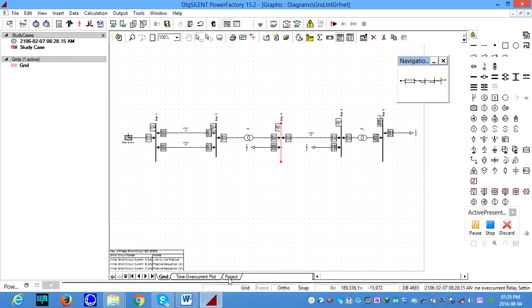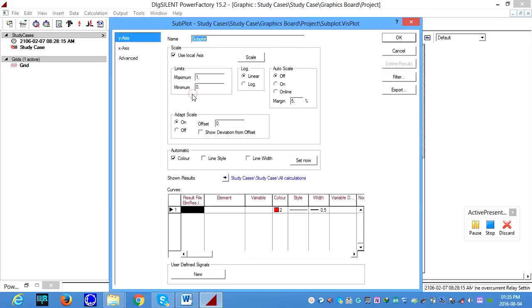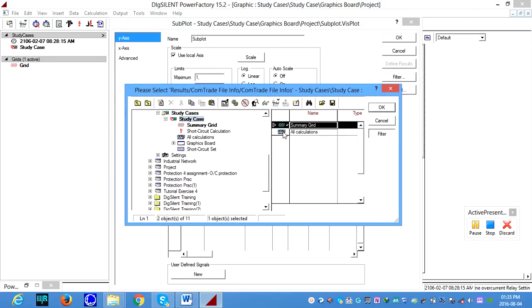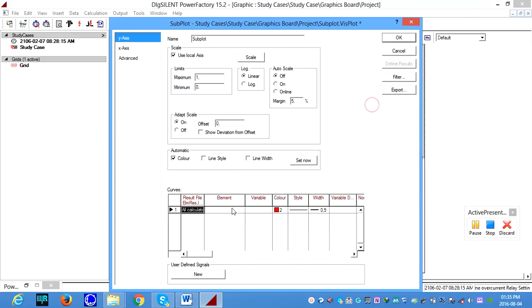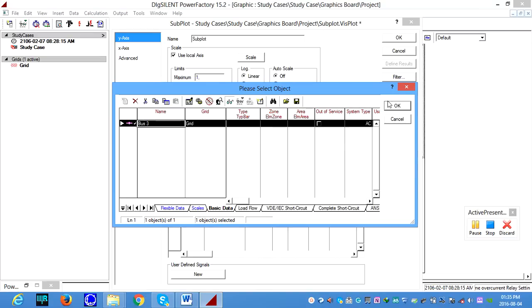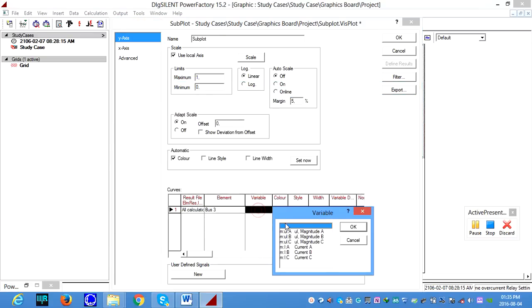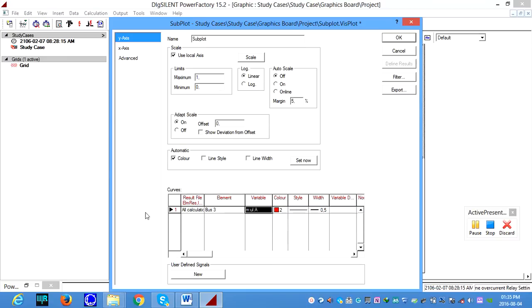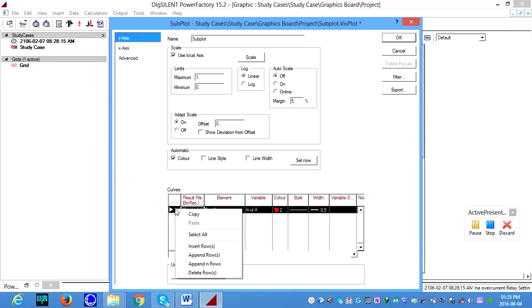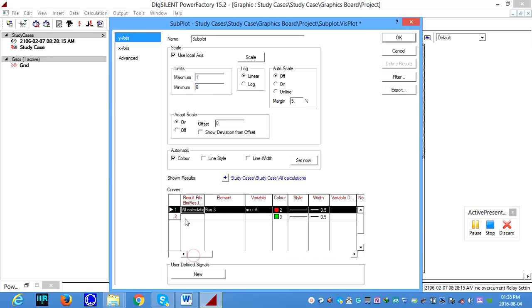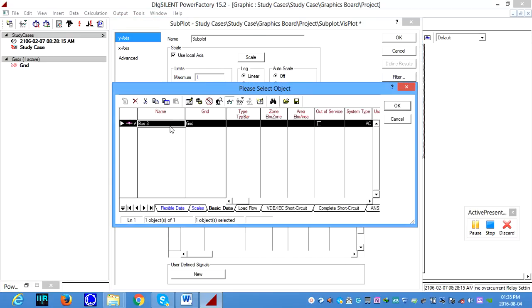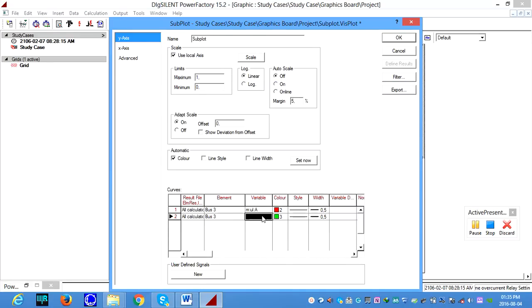Okay, now we need to go to the project. You edit here and come to select all calculations and you select your element, it's bus 3, happy, and select the variable. So what you defined on the grid you can see here. The first is your phase A and we also need phase B, so append the rows, select the same calculations and select your bus 3 and select the phase B voltage magnitude.